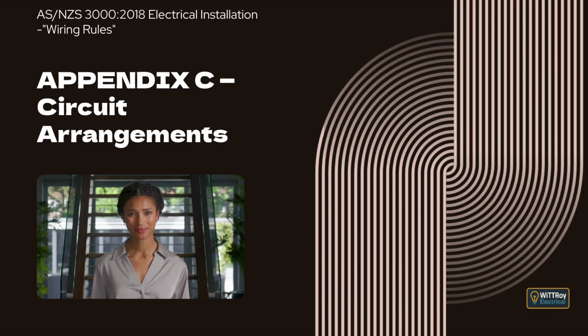Clause C2.5.2.2 Arc welding machines. This clause explains that for an individual arc welding machine, the maximum demand is taken as the full rated primary current. For groups of machines, the demand is calculated by applying full load to the two largest machines, reduced percentages to the next largest machines, and a lower percentage to all remaining machines. This reflects the reduced likelihood that all welders will operate at maximum output at the same time.